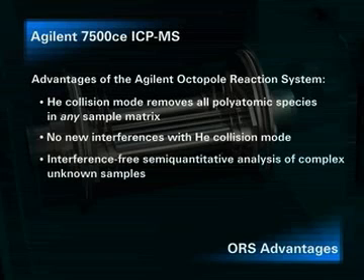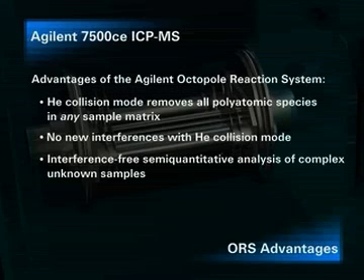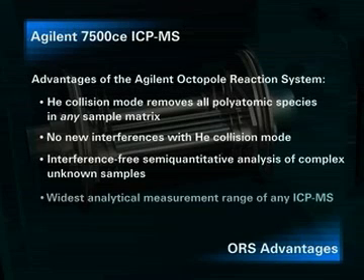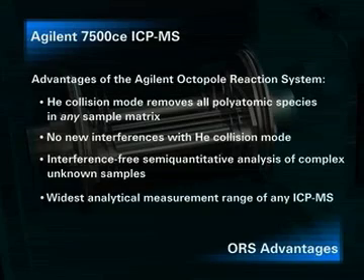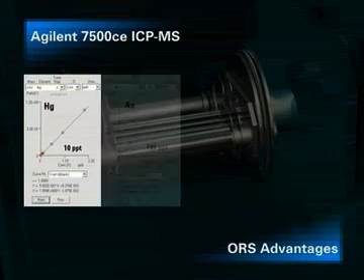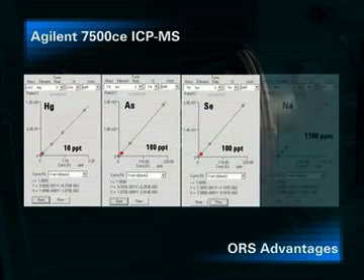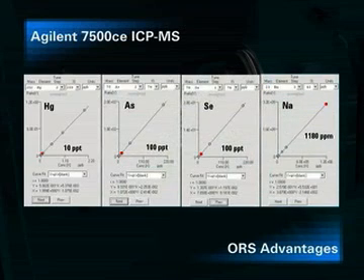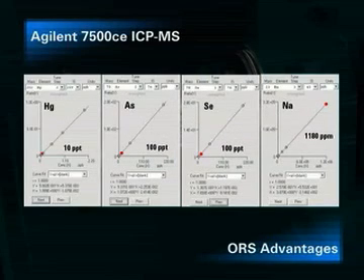Helium collision mode enables rapid and accurate semi-quantitative analysis. More than 60 elements can be measured in a completely unknown sample in approximately one minute, without the need to run calibration standards. The 7500 CE can measure mercury at single-figure parts per trillion, plus sodium at greater than 1,000 parts per million in the same analytical run. The calibration graphs show excellent linearity for mercury down to the 10 parts per trillion level, arsenic and selenium down to 100 parts per trillion, and sodium at 1,180 parts per million, all achieved in the same run. The ability to measure elements over a wide concentration range in a single analysis clearly demonstrates the power of the ORS.